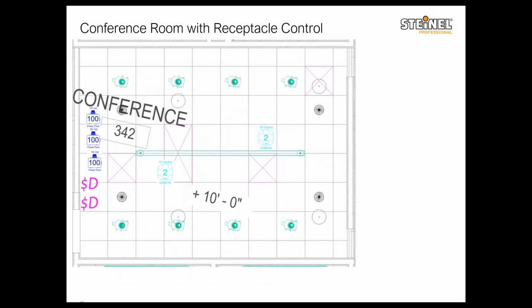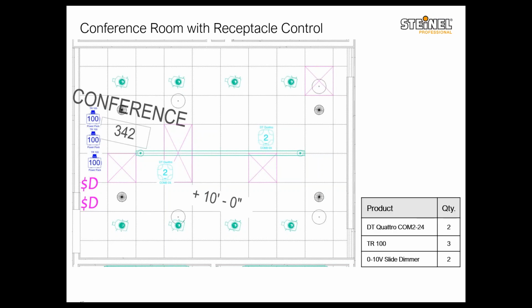Next case would be, again, the same conference room that we had before. And we have the slide dimmers, we have the plug load control and receptacle control. And here you still have two COM2-24 sensors. So even if you want to add in the HVAC integration, you can do it. But this combination here would be sufficient for receptacle control with the COM2-24 sensors. And again, we discussed the receptacle control for big open office areas in the previous slide with the HVAC integration.